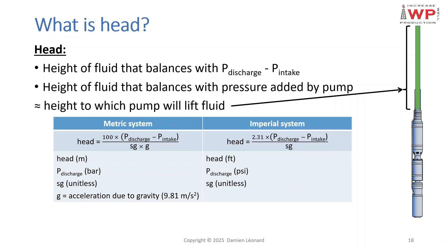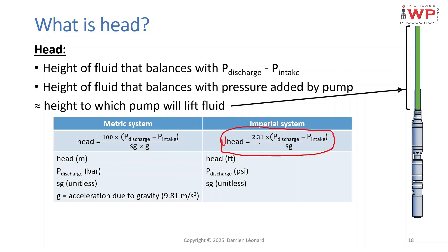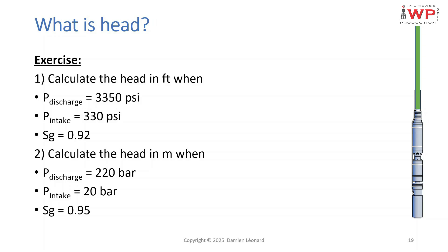To calculate head, there are two formulas: one for the metric system and one for the imperial system. In the metric system, head is expressed in meters: H = 100 × (Pdischarge − Pintake) / (SG × g). In the imperial system, head is expressed in feet: H = 2.31 × (Pdischarge − Pintake) / SG, where pressures are in psi.